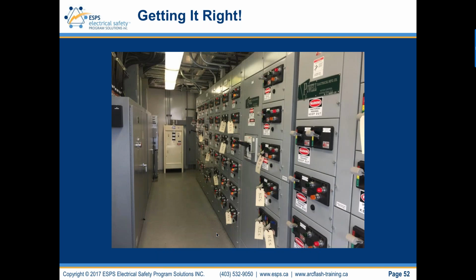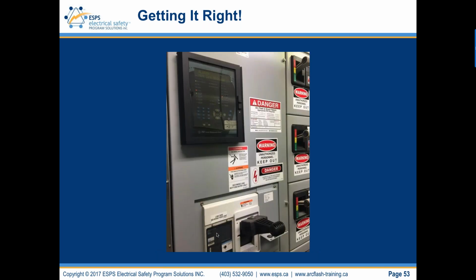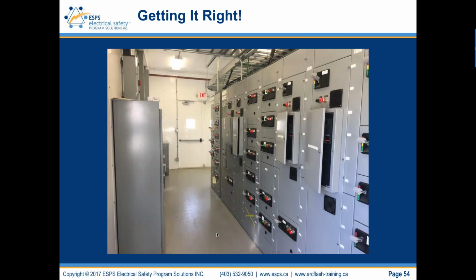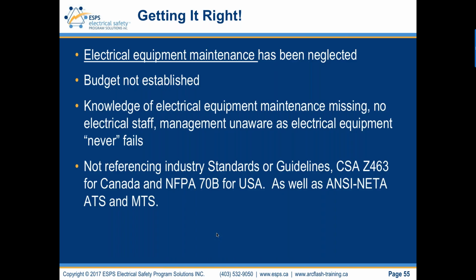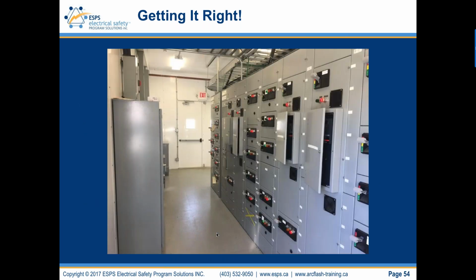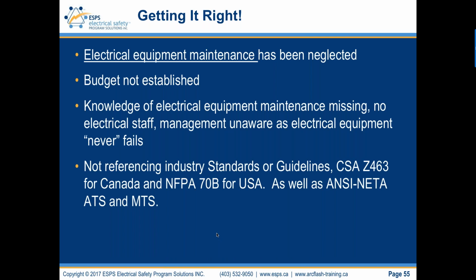Here's an instance where this MCC has a generic unauthorized personnel keep out on every bucket door. I've seen every bucket door with a detailed arc flash and shock equipment label on it. This one, look at the labeling. It's over the top. So this is another aspect of labeling. It can be exhaustive where the worker goes, well, whatever, right? Worker complacency to over-labeling will be another issue for the company. Or there are no labels. So you have some labels and then no labels. So consistency in labeling is also another concern. Electrical equipment maintenance has been neglected. So depending on where I go, the statement is false.